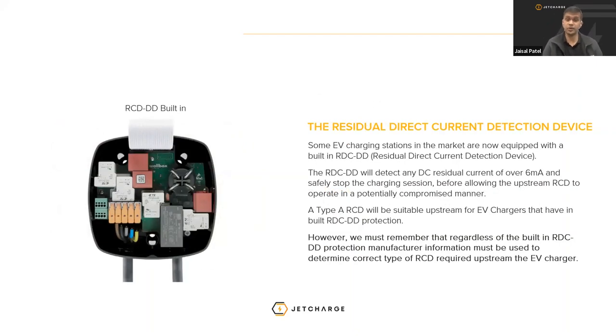How they differ is essentially the type B RCD comes with built-in DC fault protection up to over 6 milliamps. What that essentially means is that it is able to detect any DC residual current of over 6 milliamps and safely stop the charging session, which the type A RCD does not have. So when you design your charging station system, you would have to ensure that the charger that you specify either has an RDC-DD, which is essentially a residual direct current detection device.